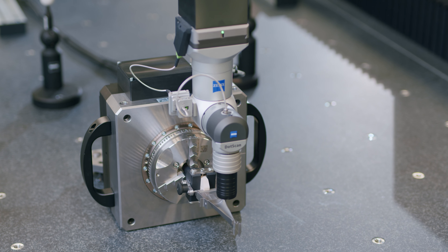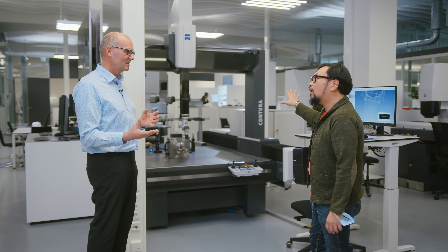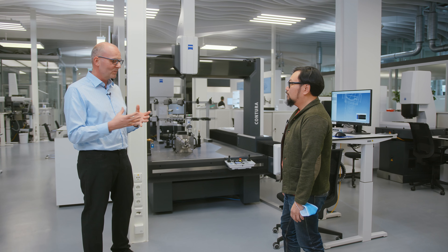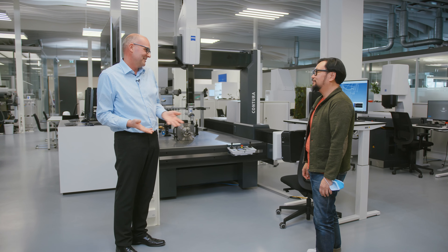We've already talked about the benefits of the new Contura, and one of those benefits is the MASS system, the MASS technology. We asked the customers and thought let's introduce the MASS system on the Contura for perfect exchange between different kinds of sensors. Before, on a Contura, you had to choose either a fixed system or indexing system — the customer had to select before and they were locked into it. Now they are absolutely open because the MASS system helps the customer to integrate sensors afterwards. We copied the technology from the Prismo to this machine.